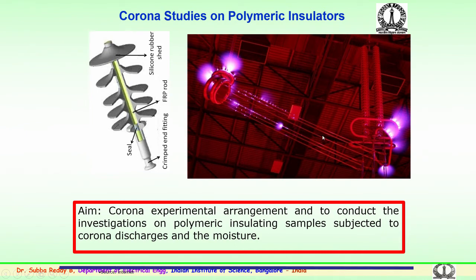So, the corona which I was mentioning could be of two types. One is the corona coming out from the hardware of the transmission system: the conductors, the corona control rings, and the other hardware. You can very clearly see here the corona control ring, and these are the insulators, two suspension insulators, twin suspension insulators.